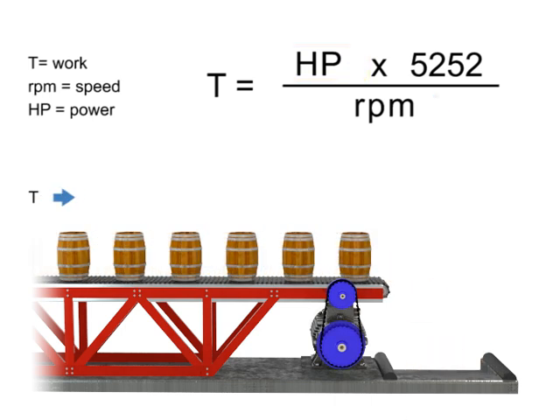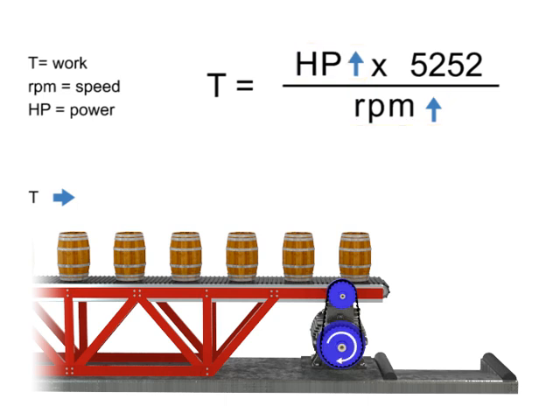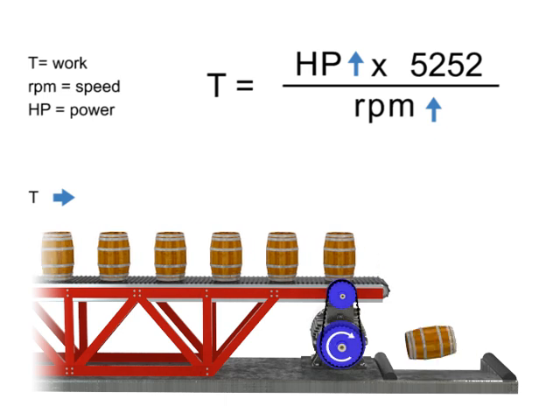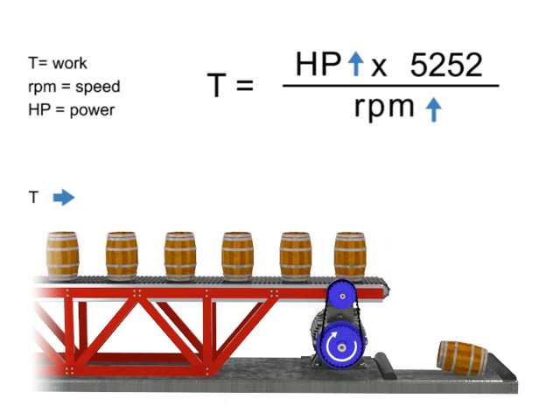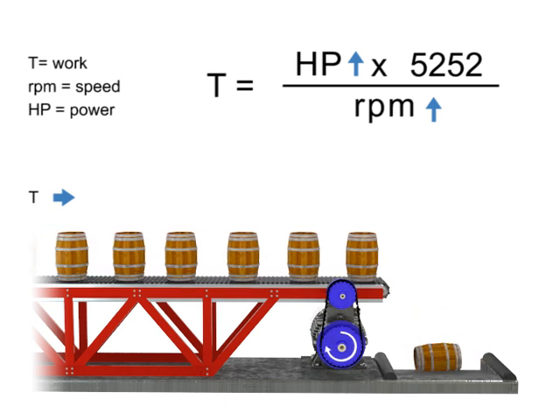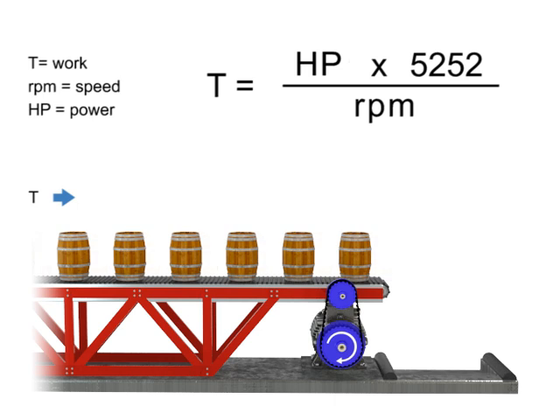Let's say we wish to keep torque constant but want to increase the production of barrels. If the torque, or number of barrels on the conveyor belt, remains constant but speed increases, then the horsepower of the motor also increases. In other words, a more powerful motor is required to produce the same amount of torque more quickly. Similarly, the opposite is true: if we wish torque to remain constant and decrease speed, then the horsepower of the motor also decreases.